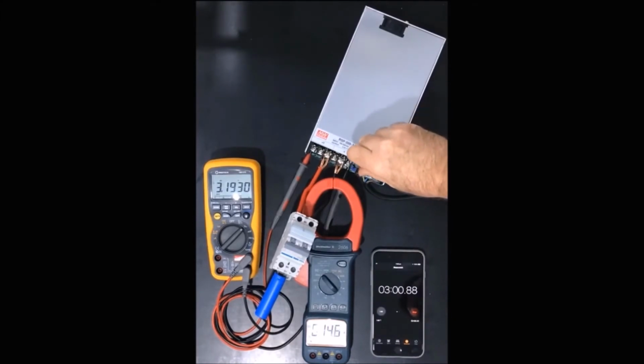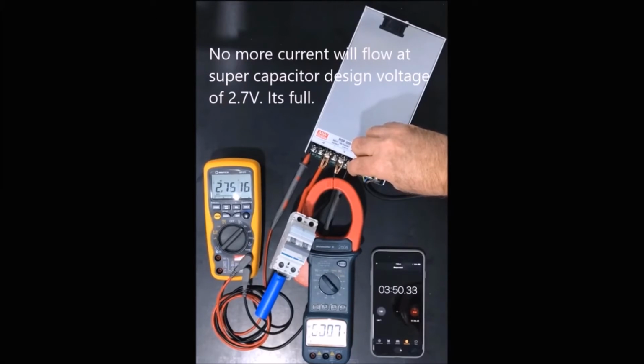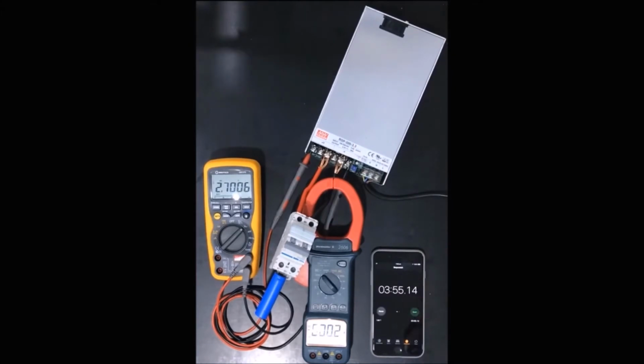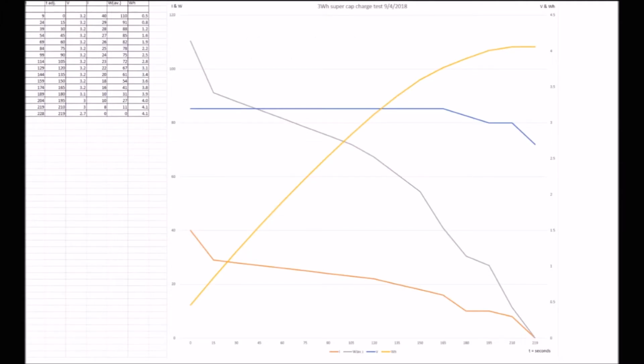So we've done cycle testing on the cells as a module, and we've done cycle testing for about 3 or 4 months with a 50-minute charge cycle. So 50 minutes to full and empty on the entire pack. The pack got to about 40 degrees Celsius and just sat there. We had a round trip efficiency of about 2% loss in each direction. So the loss of energy when you're charging it at full power continuously for 3 months on end loses very, very little energy at all, which means the pack doesn't get hot, which means you get a better outcome. There's some data from the test.